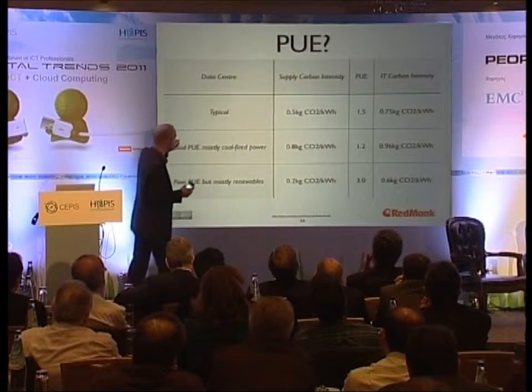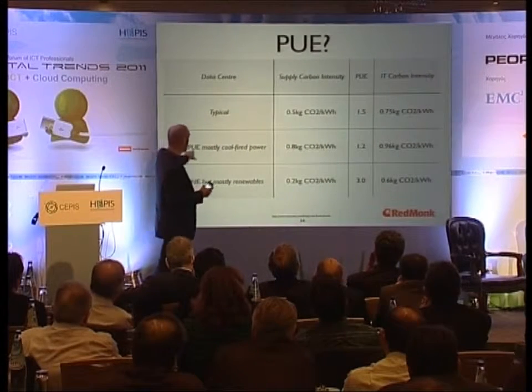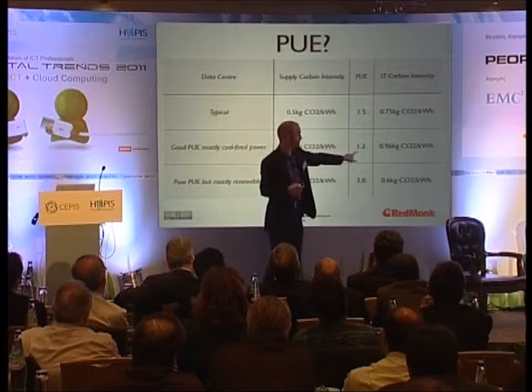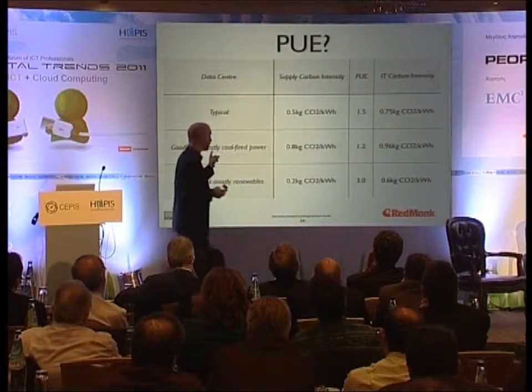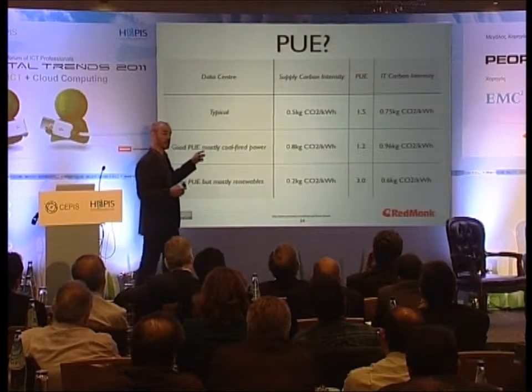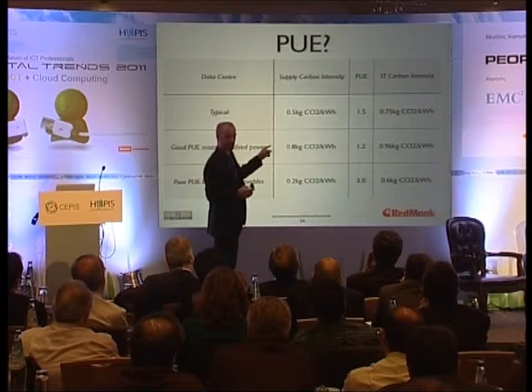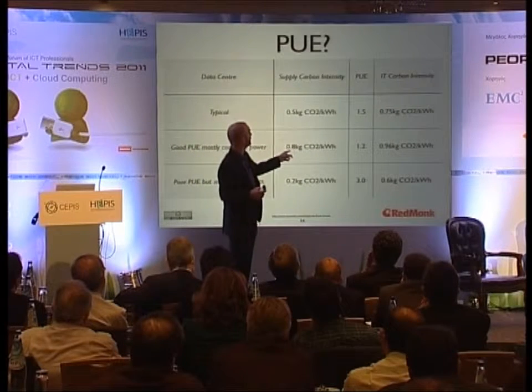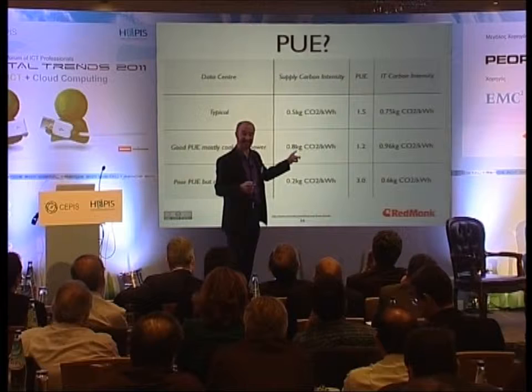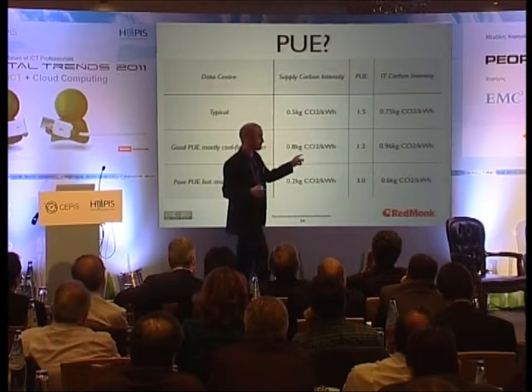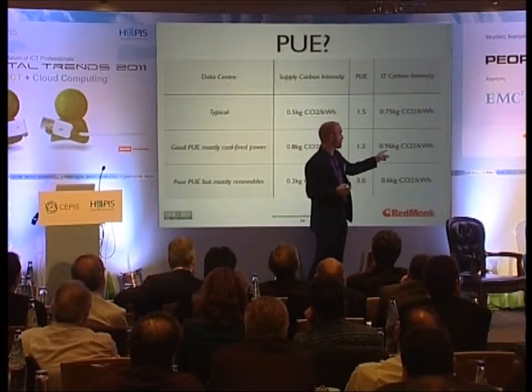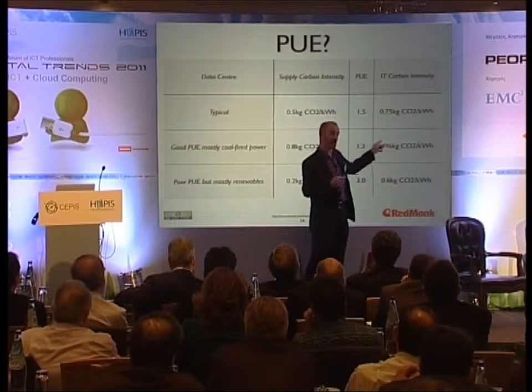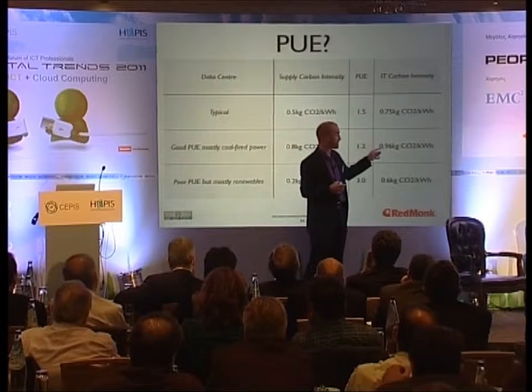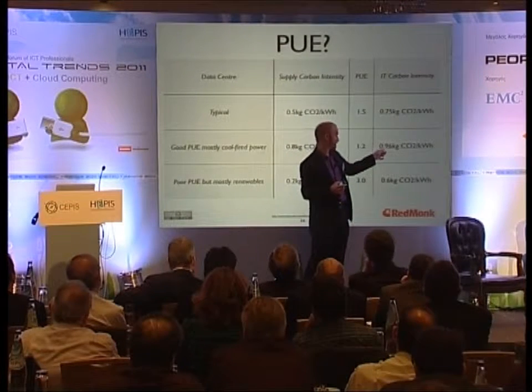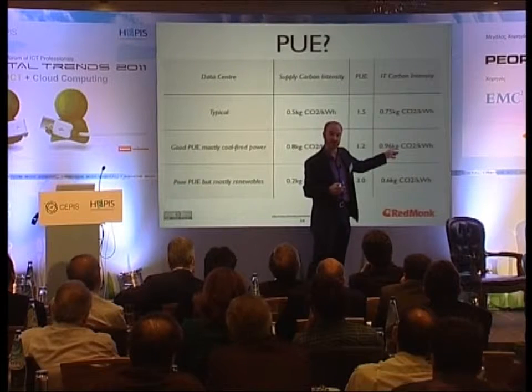So if we have a data center with a good PUE, 1.2, drawing mostly from coal-fired power with a supply carbon intensity of 0.8 kilos, then 0.8 times 1.2 means you're producing 0.96 kilos CO2 per kilowatt hour, even with a good PUE.